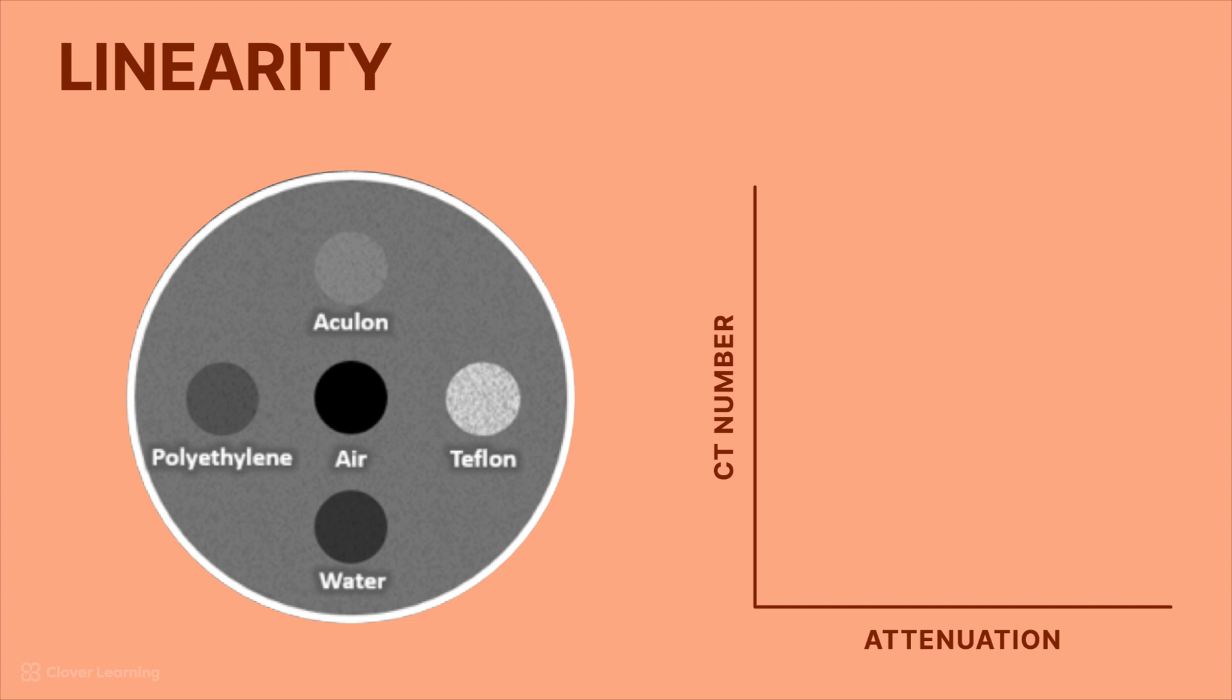As the attenuation of the x-ray beam increases, the CT number should increase by the same factor. And when we plot this relationship on the graph, we should get something that is very close to a line. And that's why it's called linearity.